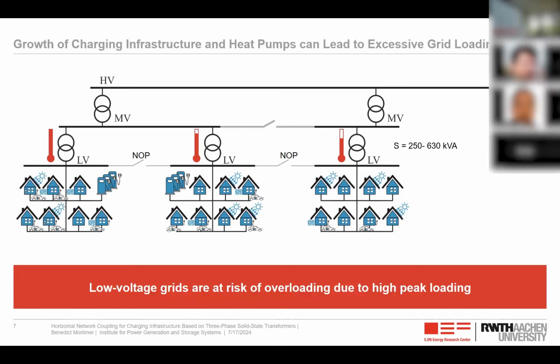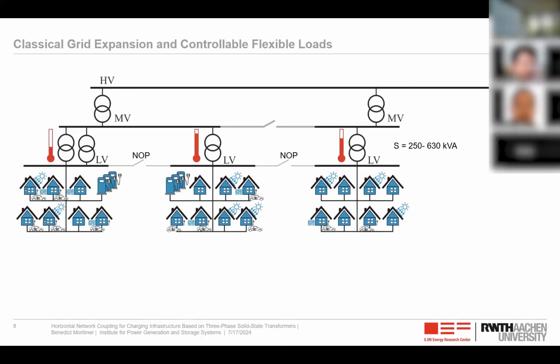So typically, to avoid this situation, we can just install new transformers or replace the existing ones with a higher power rating. But doing this, the average utilization of the installed transformers will remain quite low. And we tie up a lot of critical future resources, such as copper and steel, which are then poorly utilized.